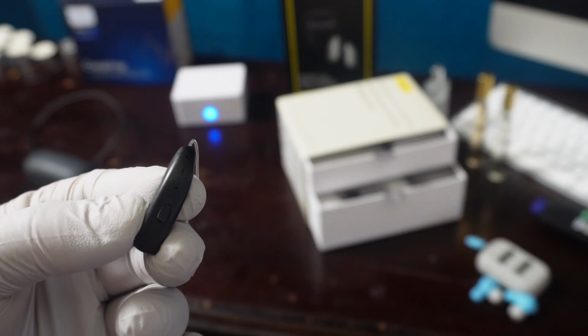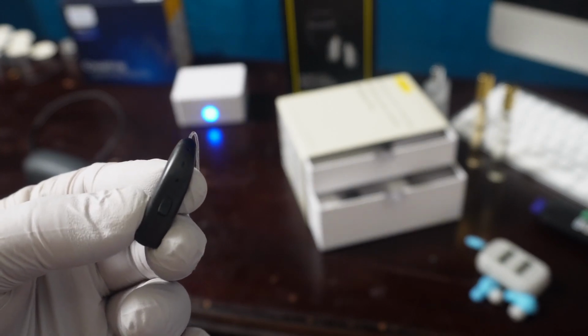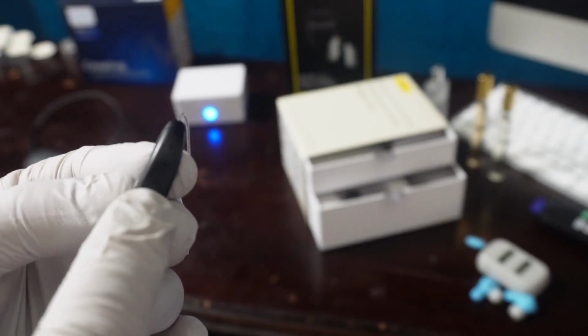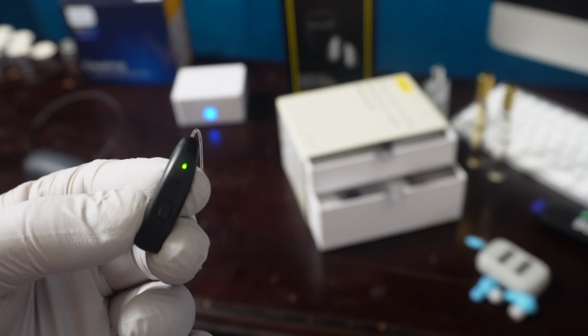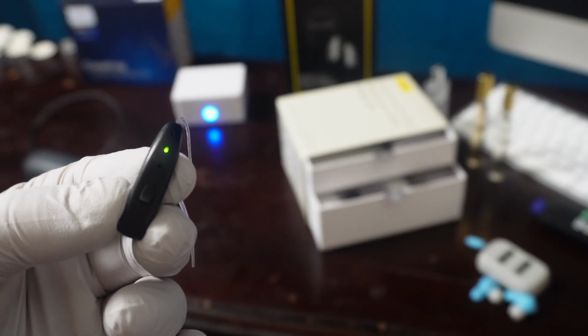With these Jabra hearing aids that I have, they only have one button on each side. Okay, so I'm going to hold down the only button that's on there. And with these, the light's going to flash 3 times once they shut off. And that's when I let go. And then I'm going to hold down the button again, and then the light's going to flash 1 time, and that's going to let me know the hearing aids are back on. And then I let go of the button. I have just turned the hearing aids off and then back on, and that is step 1. Give it a few seconds, check your app, and see if the hearing aids connect then.